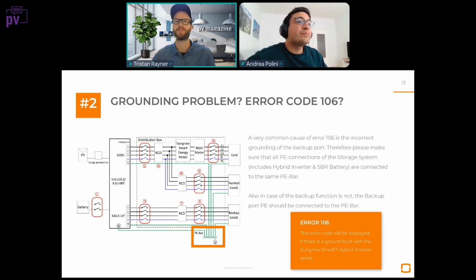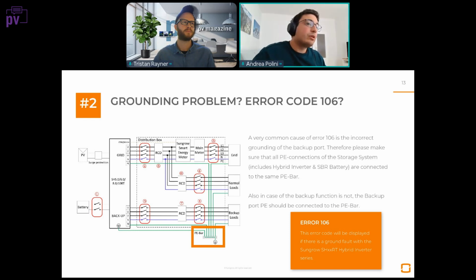We have found many times in our 3-phase hybrid plus battery setup, even in the single phase actually, that many errors are due to improper grounding of the installation. Grounding, of course, is very important, and it is even more important for hybrid inverters where you have 2 AC grids together. We are providing the normal grid connection, but also the backup grid. So a part of the house load must be connected to the backup output of our hybrid inverter in order to supply in case of a grid outage. This is the backup output. It's the second AC plug in our inverter.